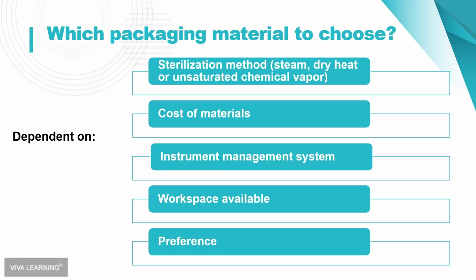In particular, dry heat, because dry heat sterilization is accomplished at a higher temperature than an autoclave or unsaturated chemical vapor. The materials that are used have to be a little more heat tolerant so that they're not going to burn up in your sterilizer. We look at cost. How much do pouches cost versus wraps if I'm using cassettes? And what type of an instrument management system am I using?